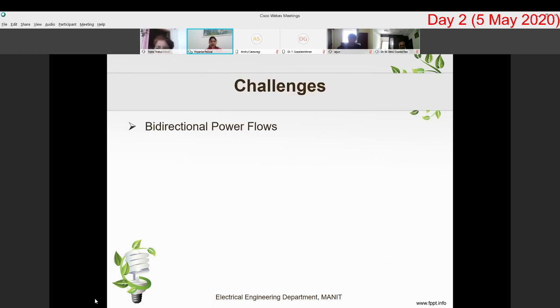There are bidirectional power flows. My distribution system was designed to handle the power flow such that it starts from the source and goes over to the load. But now I have this bidirectional power flow coming in. The microgrids are also feeding in power. The consumers, which have now become prosumers, are also feeding in power, and there is power coming from the generating station as well. So there is a bidirectional flow of power, and the distribution system has to be accordingly upgraded, especially the protection coordination, so that this bidirectional power flow can be handled.